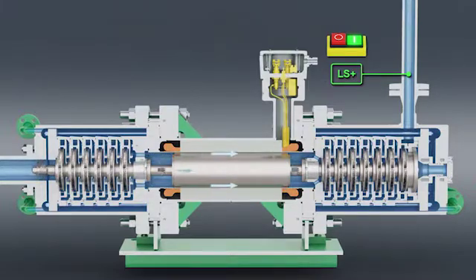The tandem design has a much better efficiency and lower NPSH requirements than any single stage centrifugal pump. The use of hydrodynamic bearings ensures a wear resistant and maintenance free operation for continuous service.